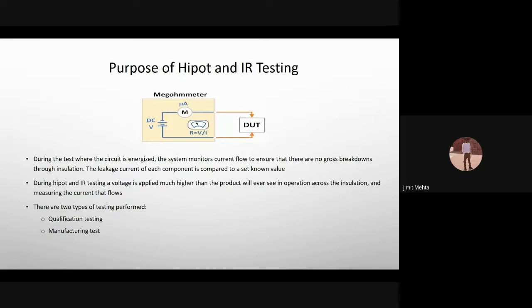There are two types of qualifications performed by this testing. Qualification testing is done at the design level, to make sure it's technically capable of preventing dangerous arcing or current passing through the product based on the insulation materials used. Manufacturing testing is done on 100% of the products being built. In both cases, you apply a voltage at multiple times the magnitude you'd expect to see from the device itself.